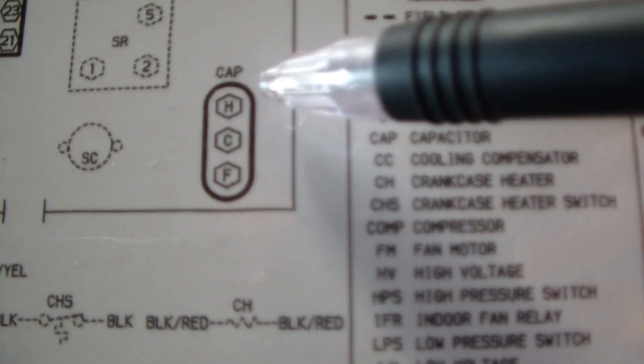So F, which stands for fan, goes to FM - fan motor. It's got one brown wire here. And going back on the parts placement, we can see where it shows an oval dual capacitor with H, C, and F.